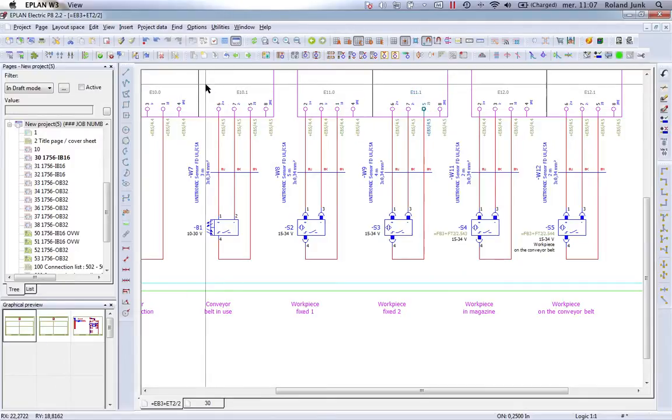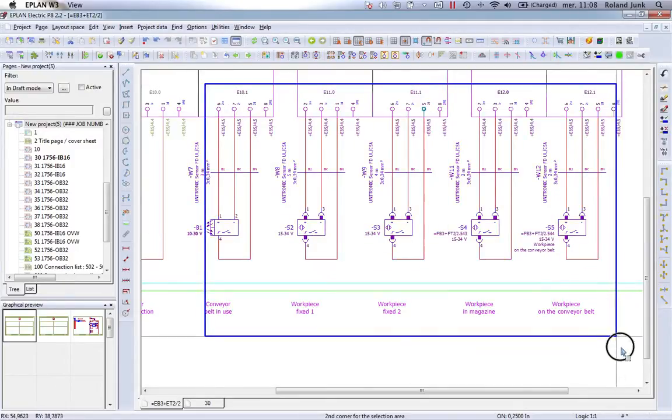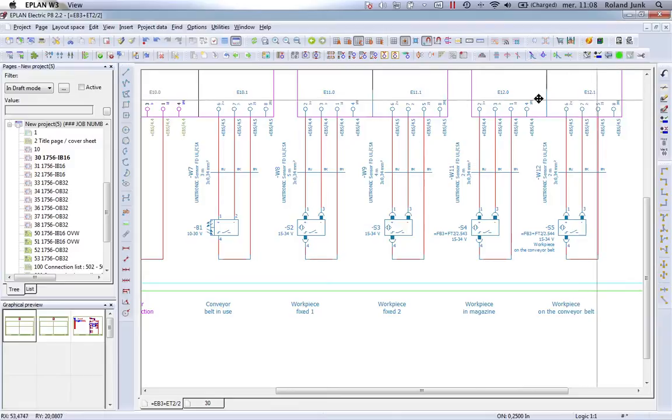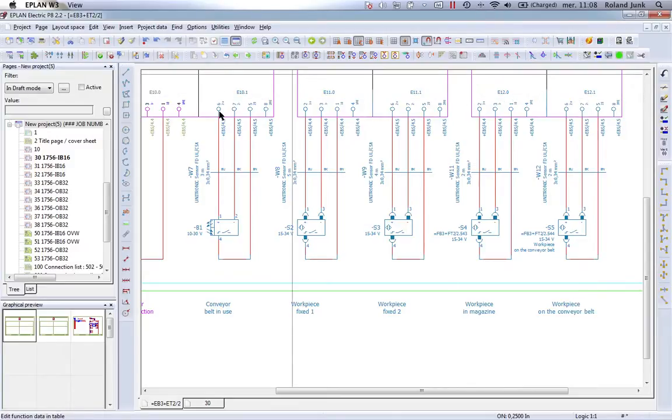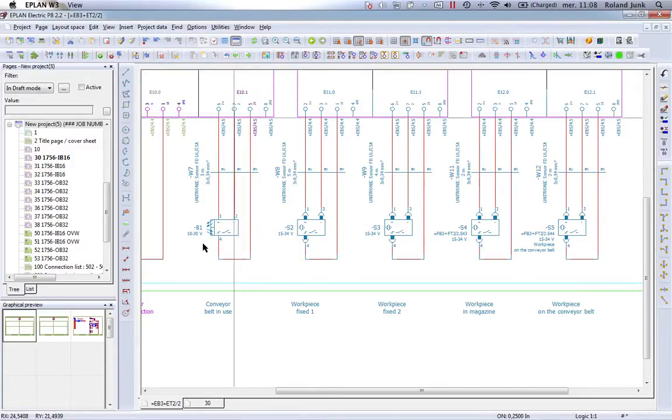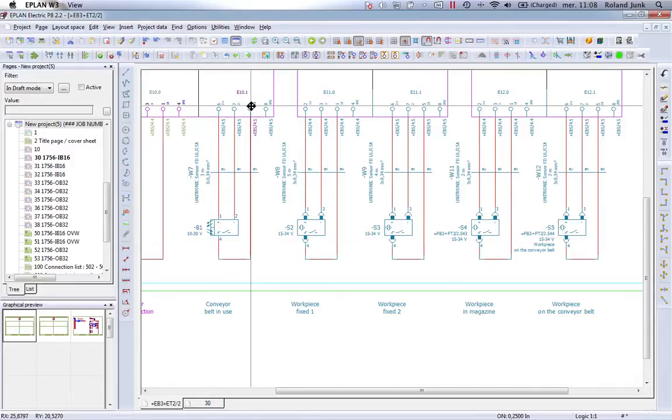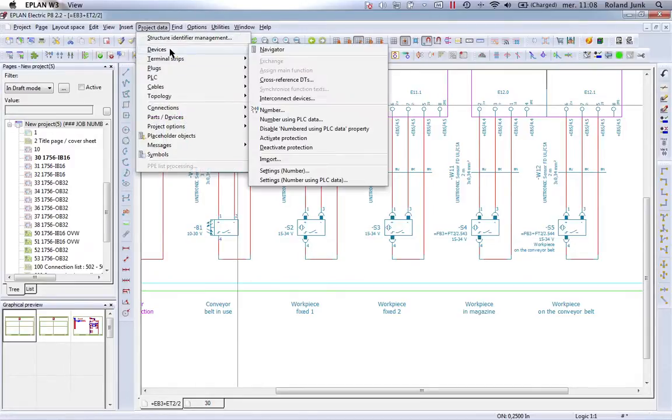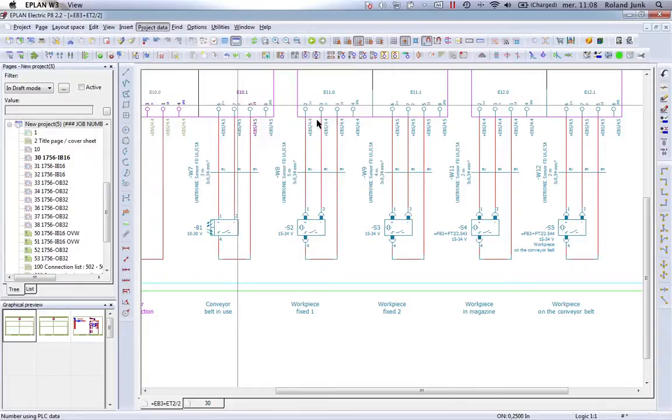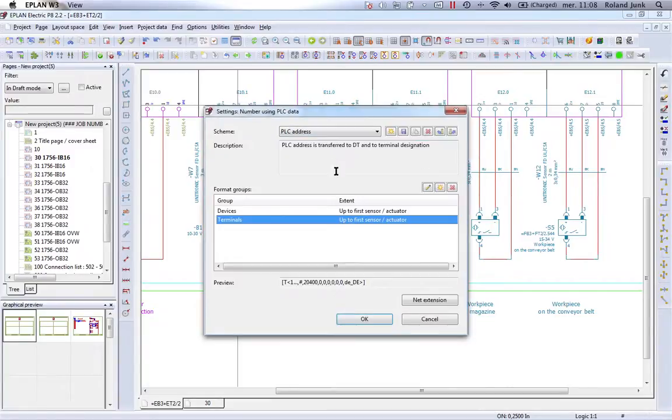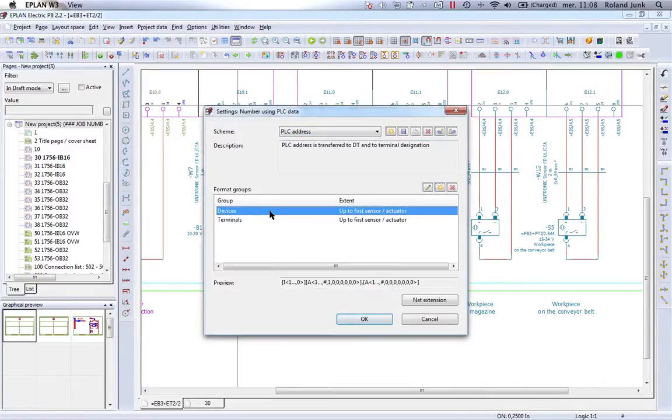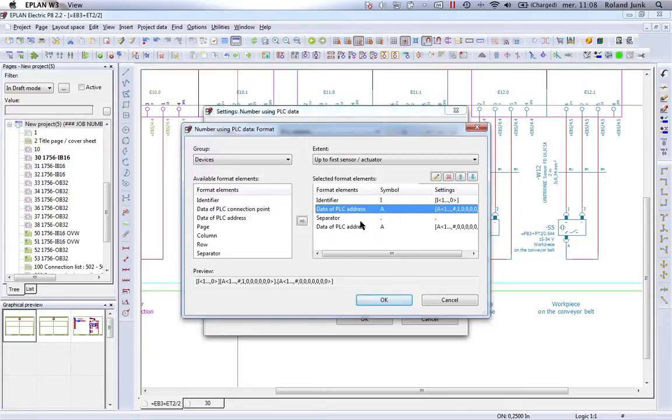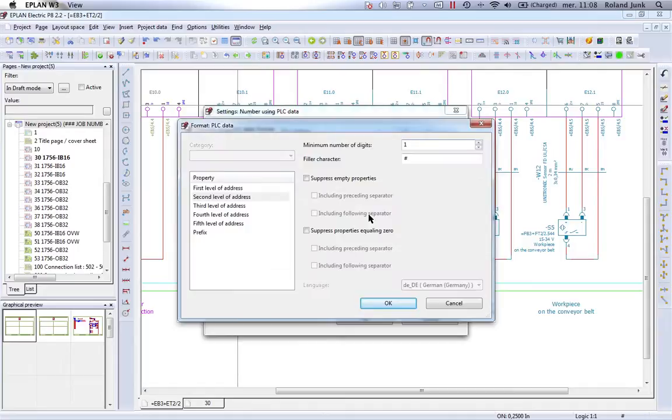If I want these devices down at the bottom to be renumbered according to a portion of the IO address, in an instance here I would like to have B10.1, I would use the same feature, device numbering using PLC data. In here, I would use a different configuration. I would basically use for devices a configuration where I keep the IO address. And because we have a dot in the address, we actually do recognize a first and second level.